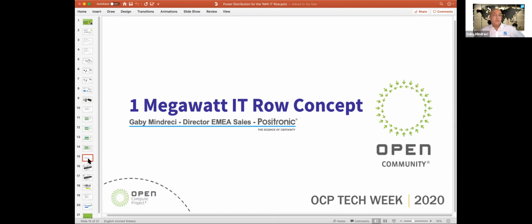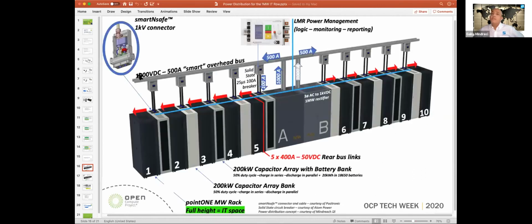So here's an advanced concept. This is a concept of a power distribution system utilizing an advanced, I'd say, objective of putting 1000 volts DC between the rectifier section into the actual racks. Now, considering for a row of 10 racks, if we want to feed 1000 volts DC to the rack, we basically need to make provisions for 1000 amps.